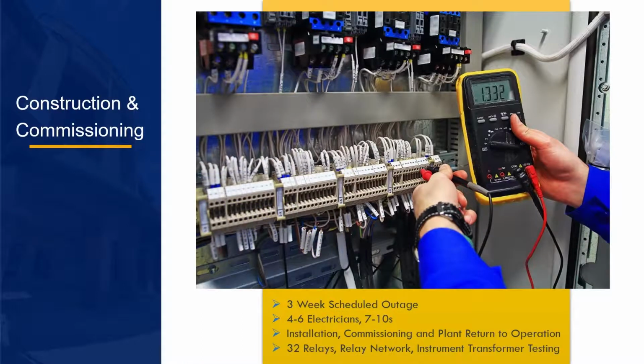The project construction was planned and completed during a routine 3-week plant outage coordinated with other plant work. The team enlisted the construction support of a third party, in which 4 to 6 electricians worked full-time for the duration of the outage. The work encompassed testing all of the protection voltage and current transformers, the replacement of all 32 relays, as well as the commissioning and return to plant operation procedures. The detailed design phase encompassed the compilation of a detailed testing and commissioning plan and construction sequence schedule.